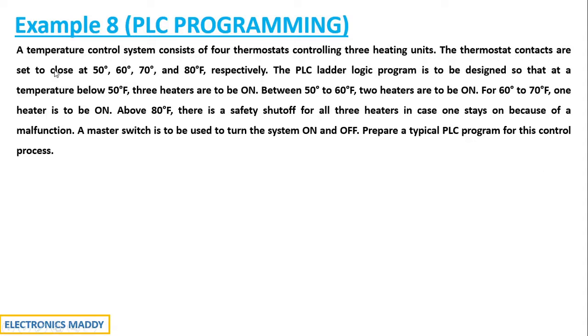The thermostat contacts are set to close at 50, 60, 70, and 80 degrees Fahrenheit respectively. The PLC ladder logic program is to be designed so that at a temperature below 50°F, three heaters are to be on. Between 50 to 60 degrees, two heaters are to be on. For 60 to 70 degrees, one heater is to be on. Above 80°F, there is a safety shutoff for all three heaters in case one stays on because of a malfunction. A master switch is to be used to turn the system on and off.